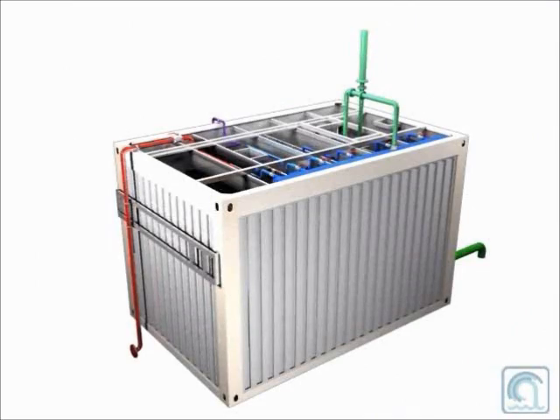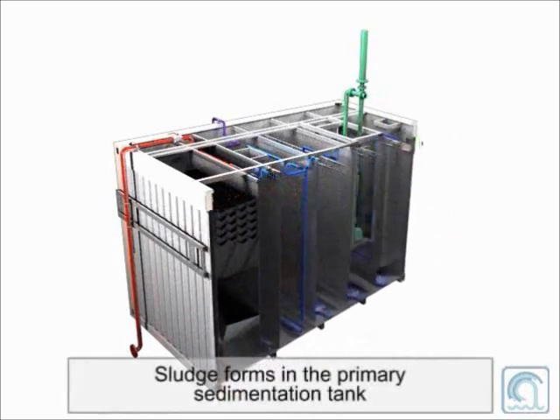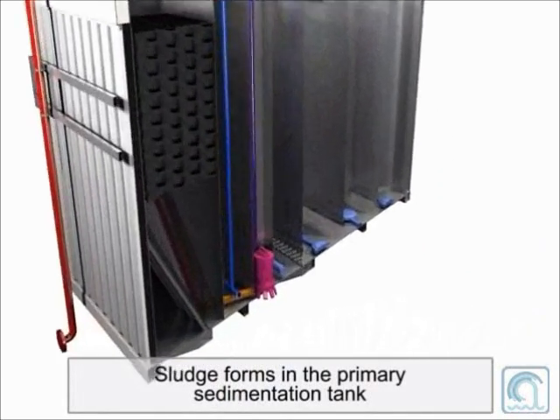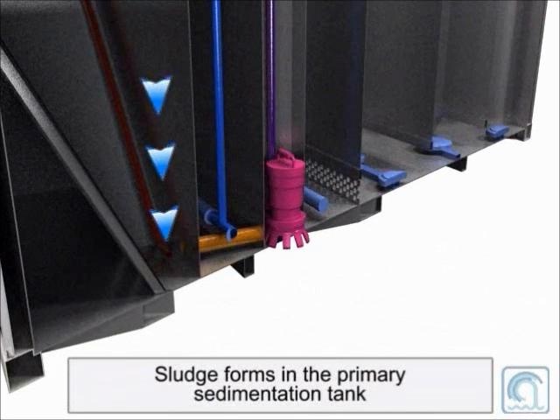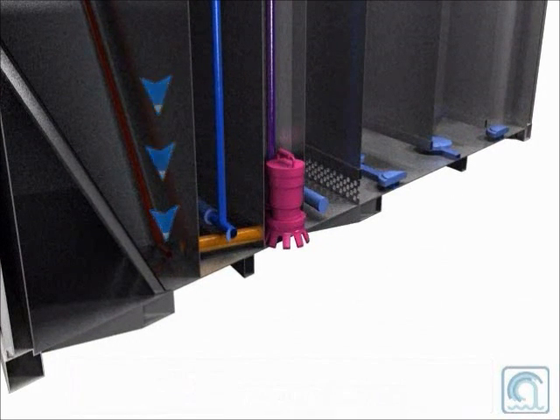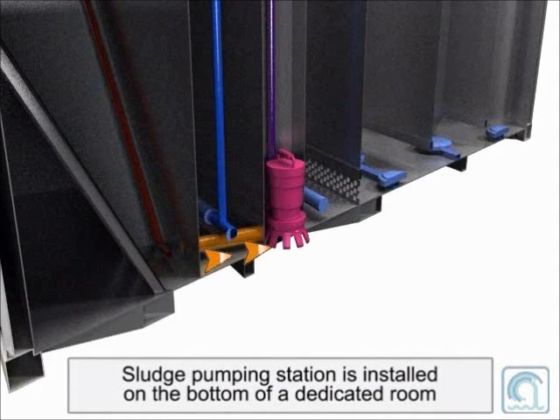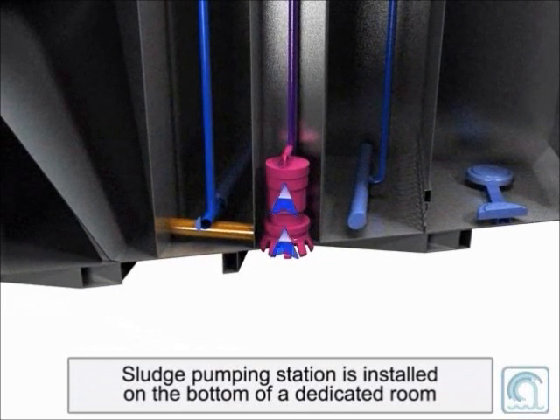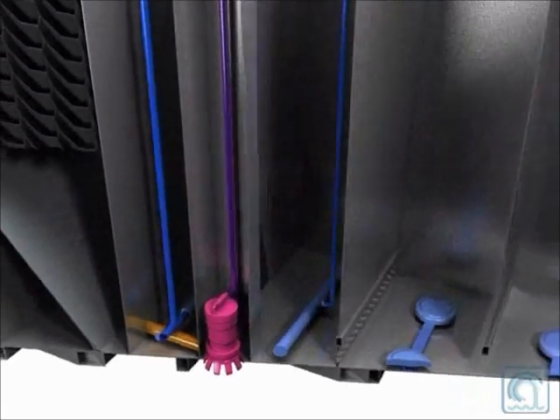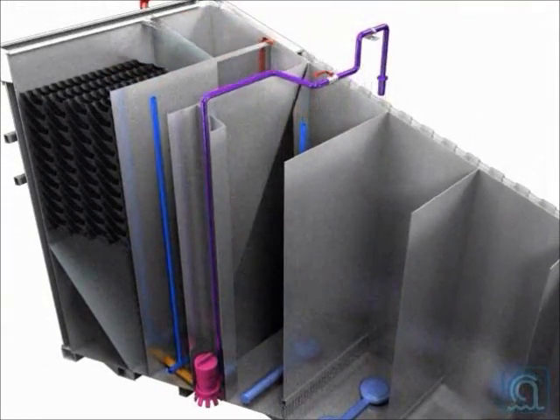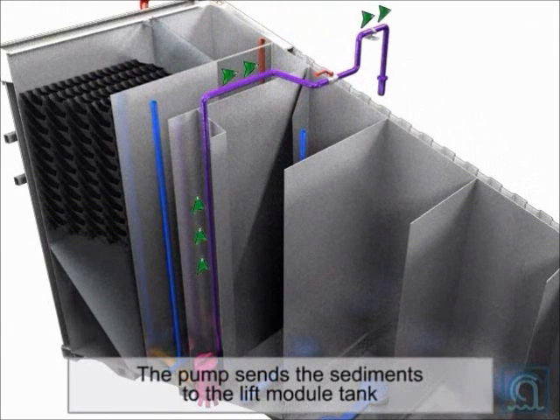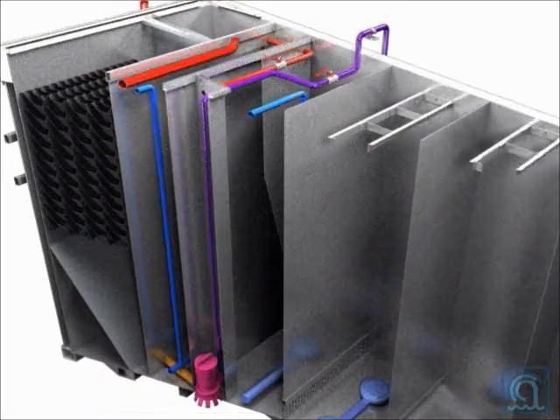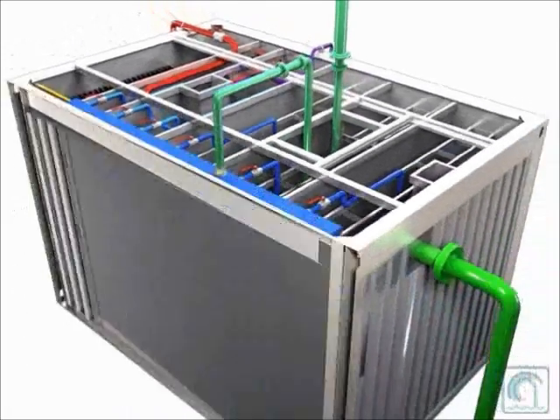Inside the treatment plant, the sludge formed in the hopper bottom of the primary sedimentation tank flows by gravity to the sludge pumping station. The sludge transfer pipe passes through the pre-aeration chamber and leads to the pumping station, which is located in a dedicated compartment on the bottom of the first aeration chamber. The pump moves the solids back to the lift station. If necessary, the sludge can be sent to an optional dewatering process.